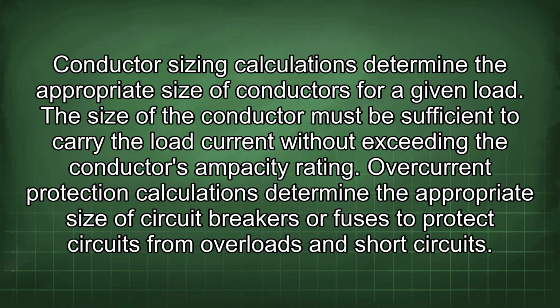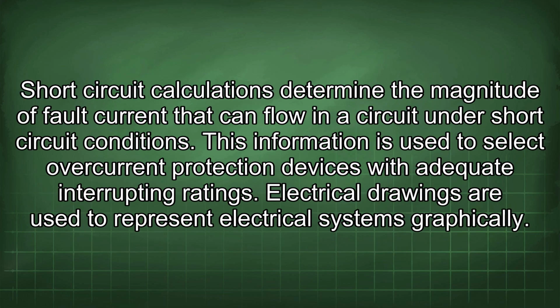Overcurrent protection calculations determine the appropriate size of circuit breakers or fuses to protect circuits from overloads and short circuits. Short circuit calculations determine the magnitude of fault current that can flow in a circuit under short circuit conditions. This information is used to select overcurrent protection devices with adequate interrupting ratings.